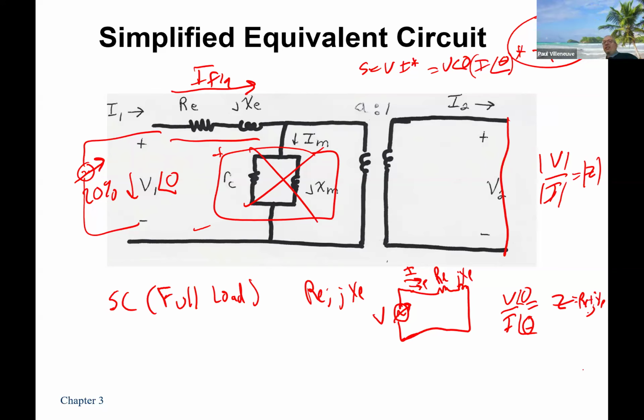So the short circuit and no load tests, the short circuit or full load test, you've got to measure three things: voltage, current, and power. And you're putting a short circuit on the output and you're slowly turning the voltage up. By the way, I can do this test on either the primary or the secondary. So the question is, should I run the test on the primary side or should I run it on the secondary side?